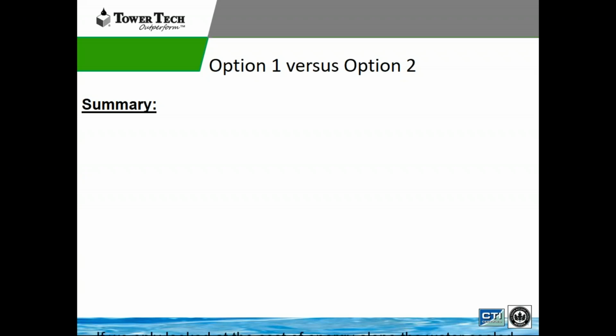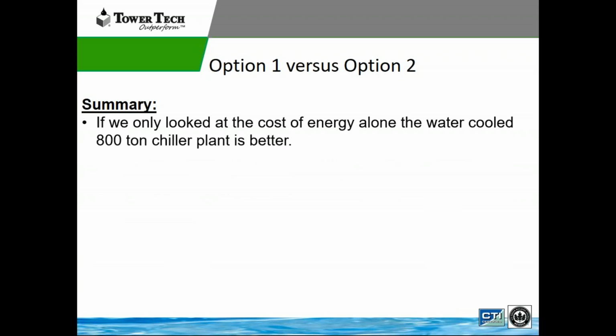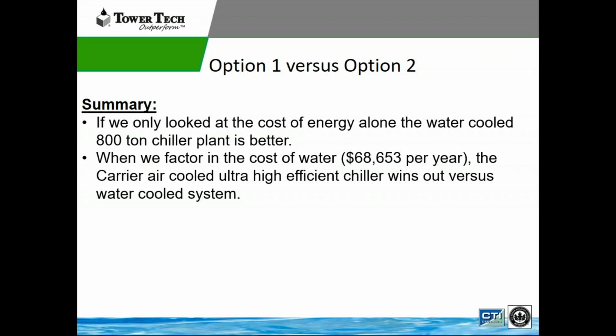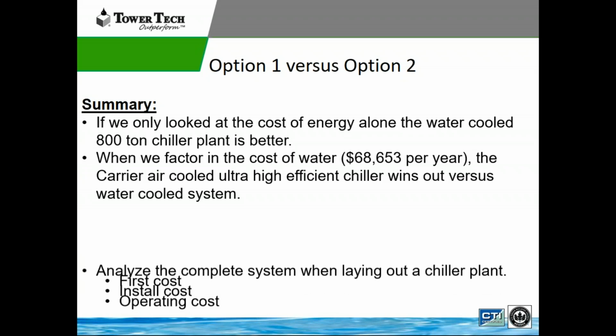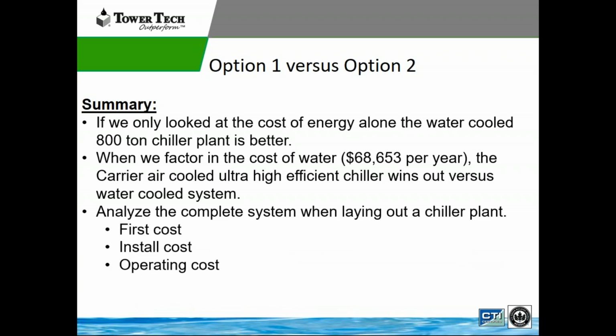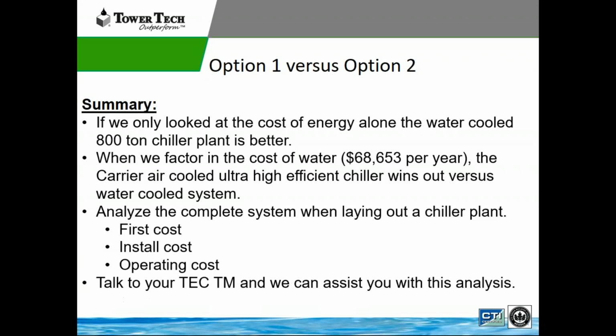So from a summary standpoint, option 1 versus 2, if we just looked at energy cost alone, the water-cooled plant would have won. However, when we factor in water cost, obviously the ultra high efficiency air-cooled, because air-cooled machines have gotten awful efficient, in this case the air-cooled machine wins, okay? When we analyze the complete system, you have to analyze the complete system. Let's look at first cost, install cost, and operating costs. Now, operating costs include the water and the electricity and the maintenance, okay?